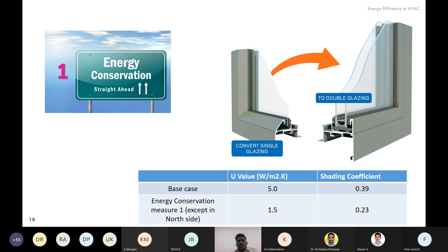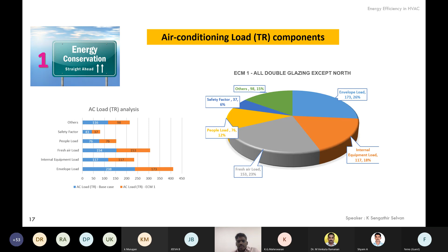So now, by changing the fenestration, we have reduced the envelope load by 26%. And the fresh air load, yeah, it is almost the same. I think the envelope load, instead of 238 TR, has now been reduced to 173 TR. But there is no change in internal equipment load or fresh air load and all. So mainly the envelope load, by changing the single glazing to double glazing in our base case, we could save around 50 TR, which is around 10% of the entire load. We could do that actually.